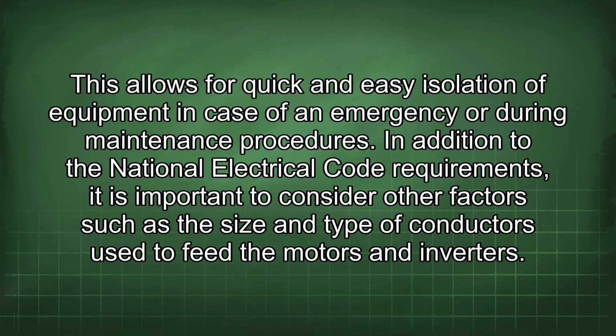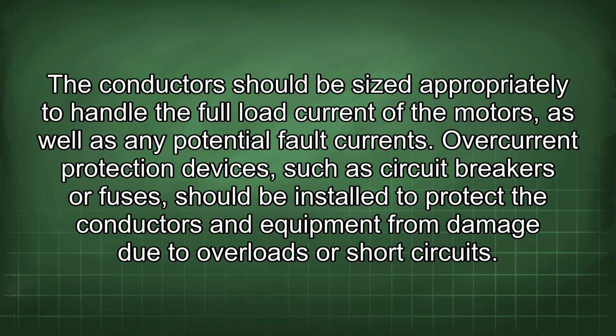In addition to the National Electrical Code requirements, it is important to consider other factors such as the size and type of conductors used to feed the motors and inverters. The conductors should be sized appropriately to handle the full load current of the motors, as well as any potential fault currents. Overcurrent protection devices, such as circuit breakers or fuses, should be installed to protect the conductors and equipment from damage due to overloads or short circuits.